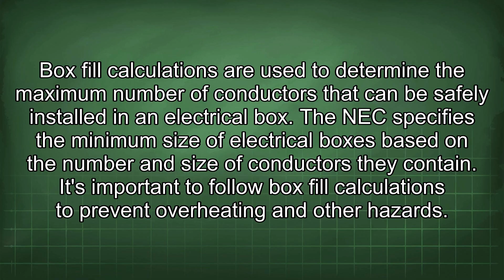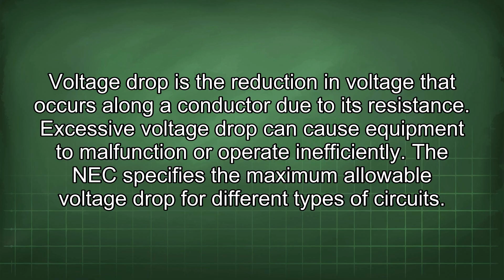Voltage drop is the reduction in voltage that occurs along a conductor due to its resistance. Excessive voltage drop can cause equipment to malfunction or operate inefficiently. The NEC specifies the maximum allowable voltage drop for different types of circuits. It's important to calculate voltage drop to ensure that the voltage at the load is within acceptable limits.